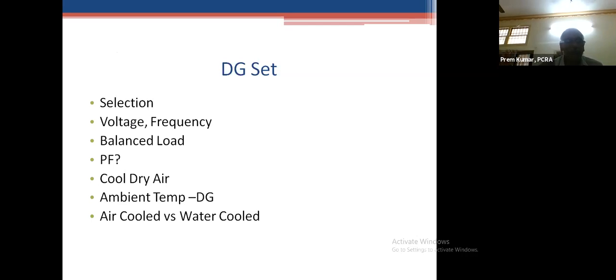Improving the power factor up to 0.95, 0.93, we can substantially save the fuel. But ensure you don't run it in leading power factor. APFC will be a good option. Ensure the power quality is harmonic free, or go for filters. Detune filter could be a good option.